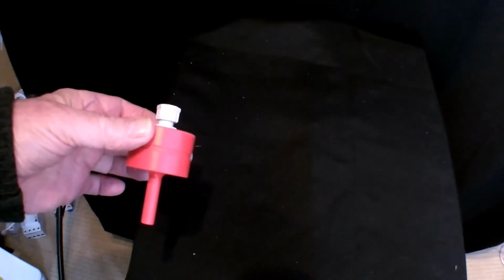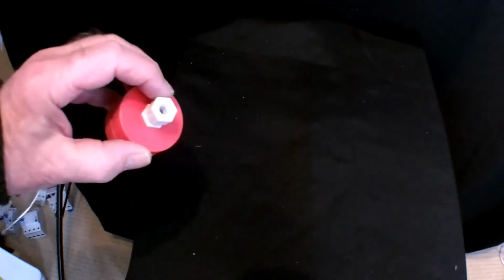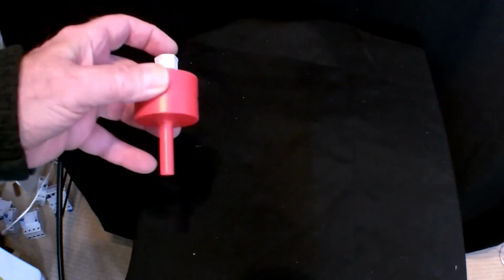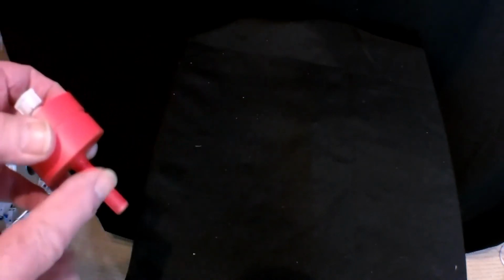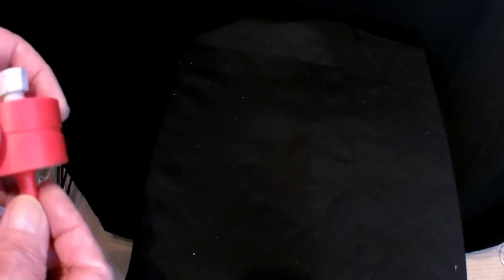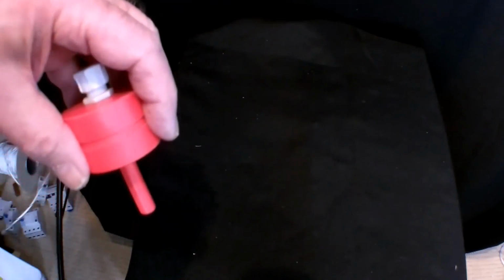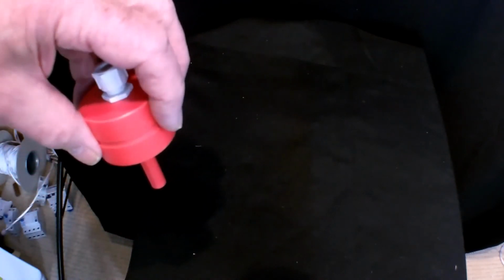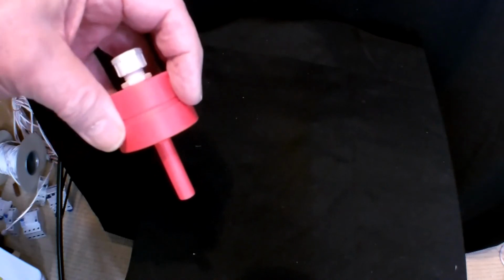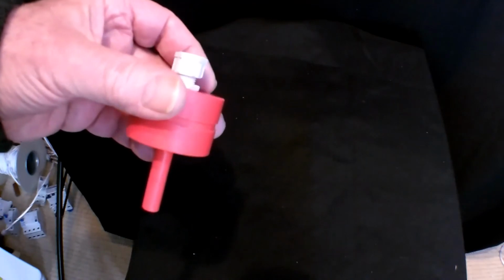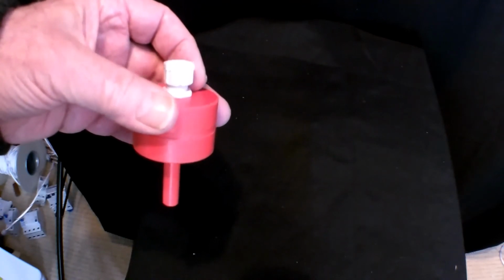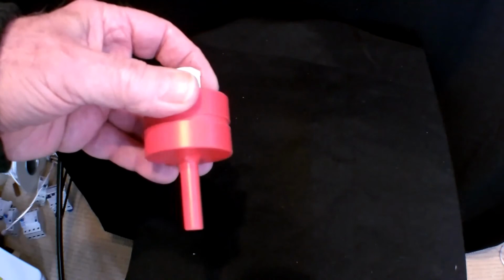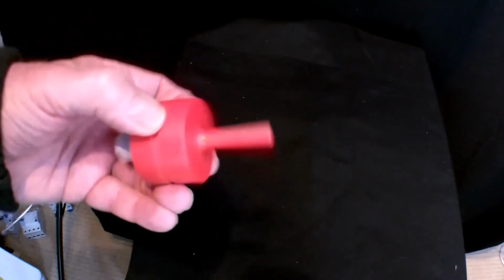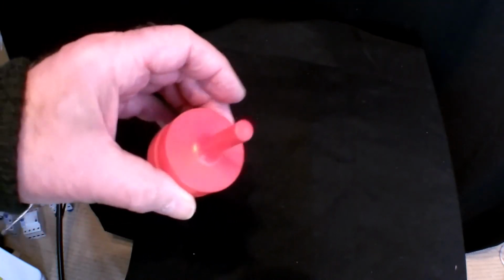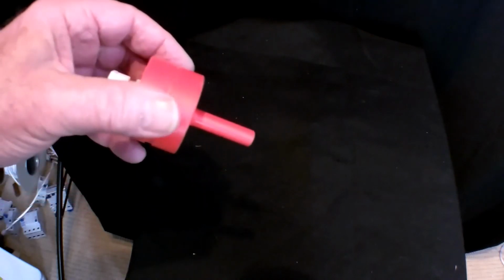This is our 1.5 inch thermal well. There's a cable gland on the top. It's very important that the sensor is actually pushed down to the bottom of here. It slides straight into a 1.5 inch T. It's got a glue ring around it, which we found very effective. They're available in 50mm, 1.5 inch, and we have supplied a few at 40mm for one particular spa company. Nice and easy, quick to do, and gives you a true temperature.